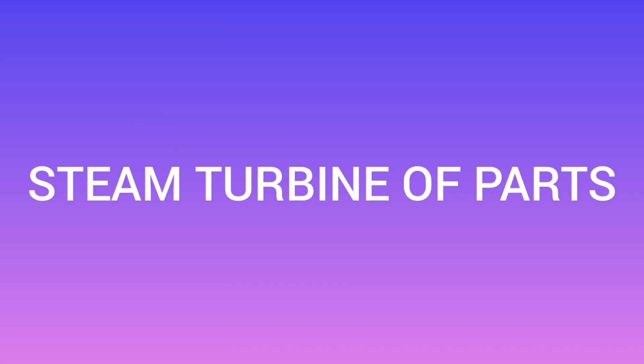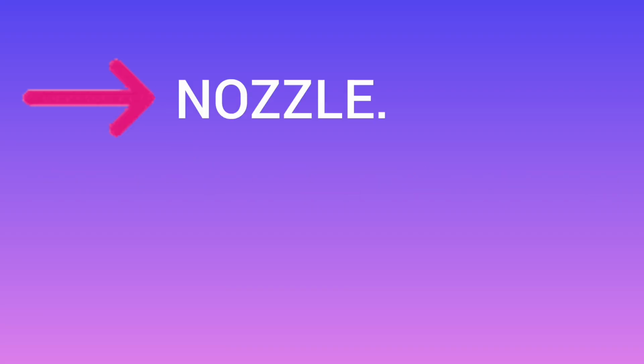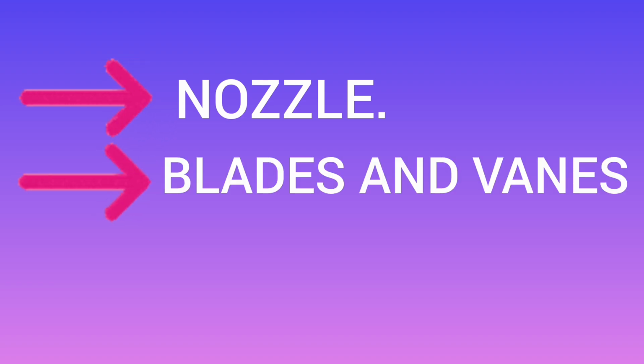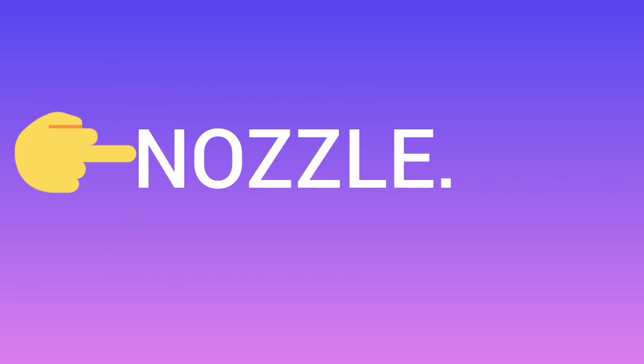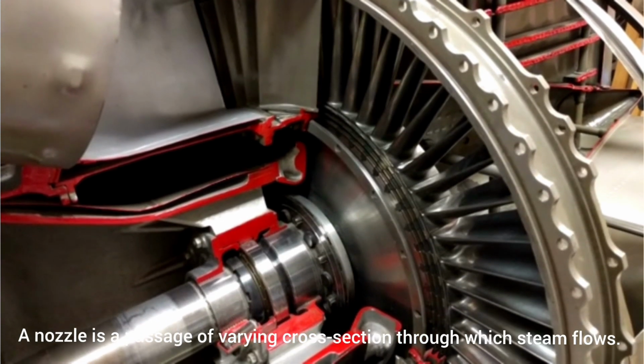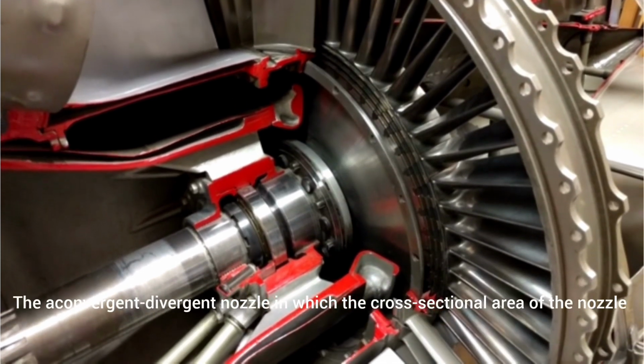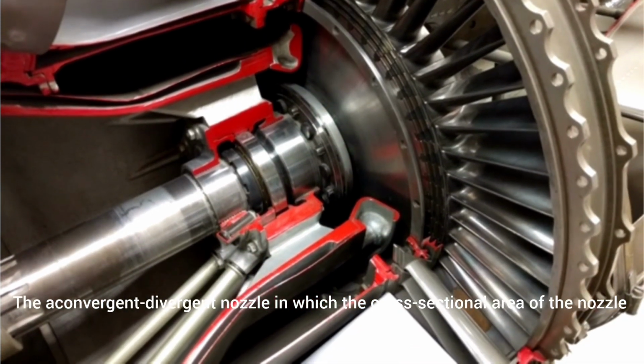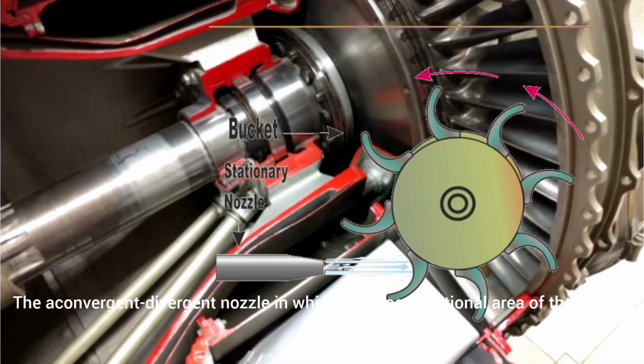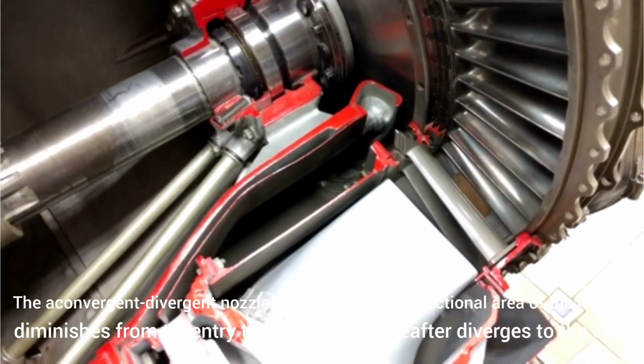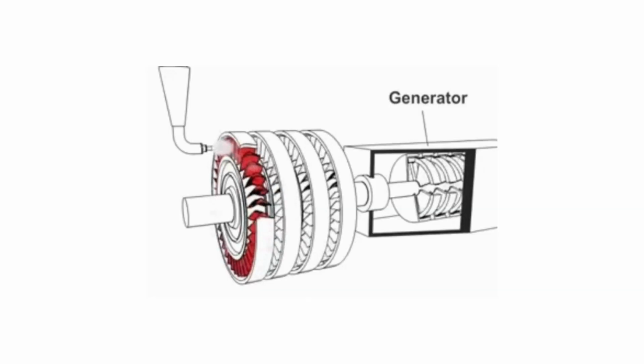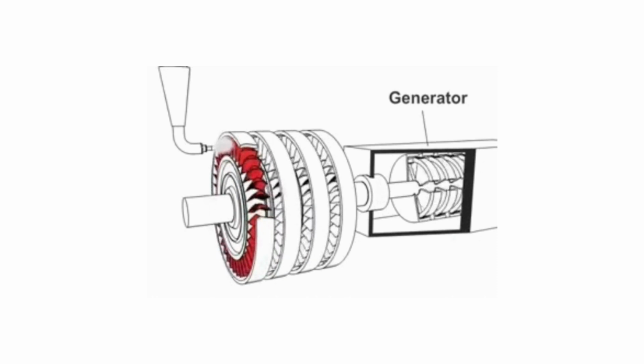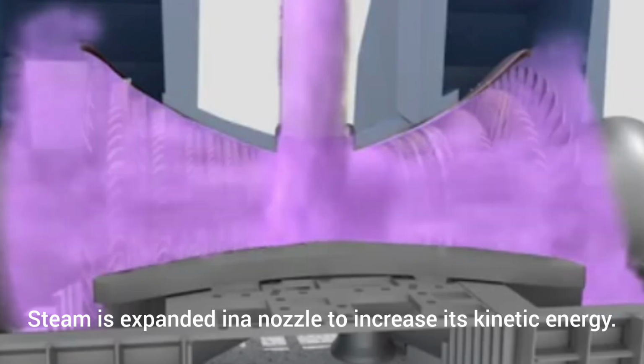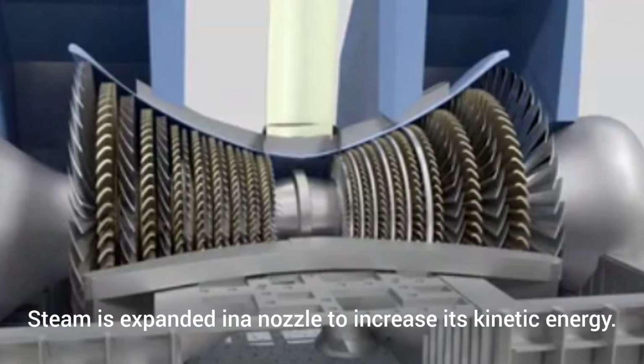The details regarding the principal parts of the turbine are discussed briefly: nozzle, blades and vanes, and casing. Nozzles. A nozzle is a passage of varying cross-section through which steam flows. A convergent-divergent nozzle is one in which the cross-sectional area diminishes from the entry to the throat and thereafter diverges to the exit. Steam is expanded in a nozzle to increase its kinetic energy.